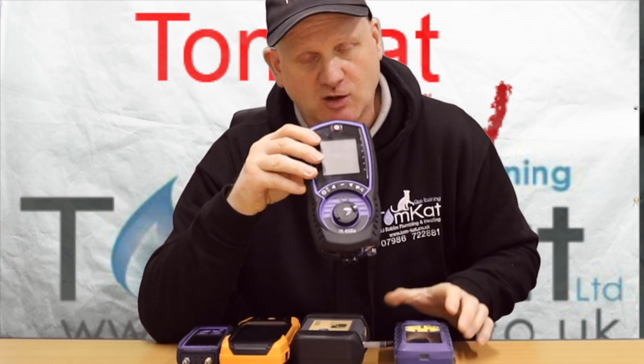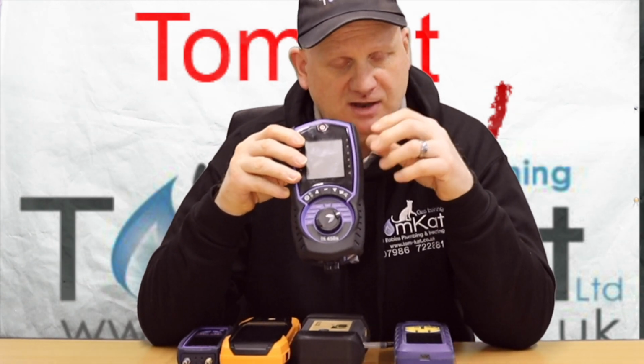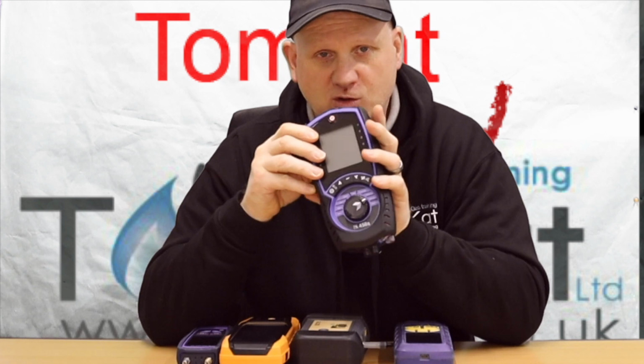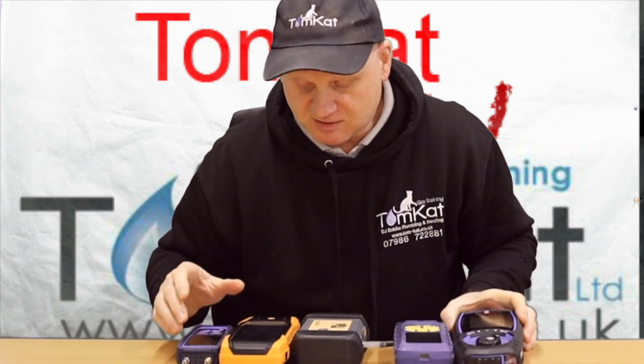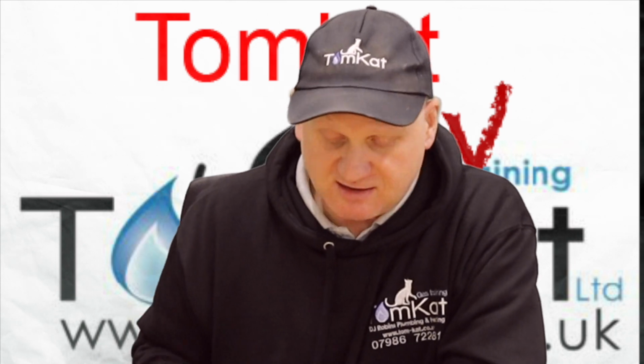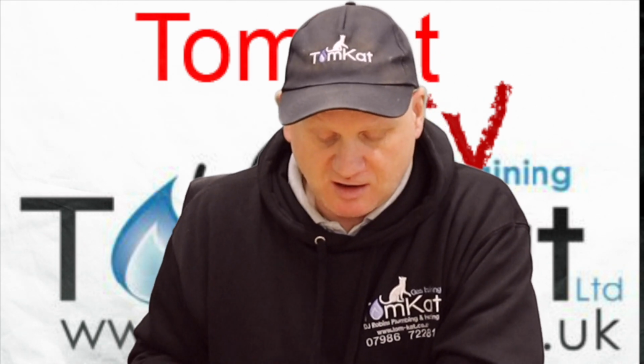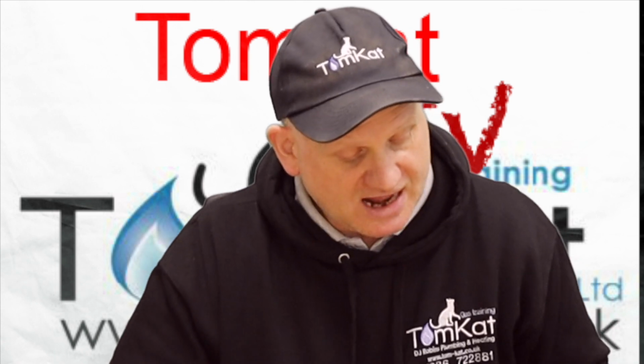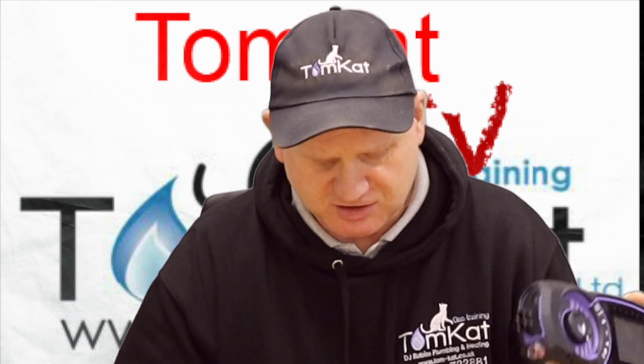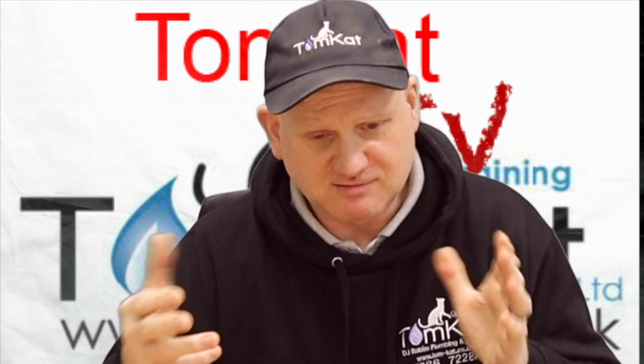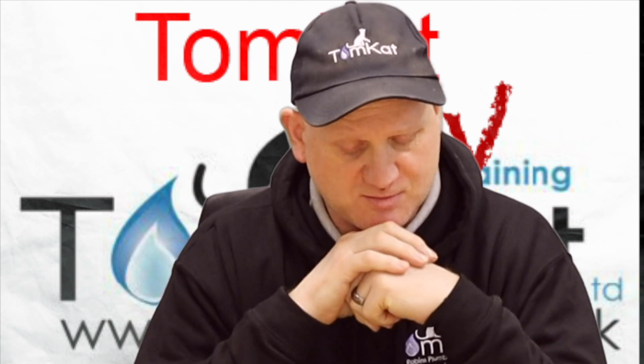If you do watch the video on which is the best between the bluelyzer, Kane and Anton, you'll find how quick this does come back. But saying that, the bluelyzer one, I sent it away for calibration on Monday and it came back Thursday. So that was a good turnaround. And I don't know how long these take to come back. So knowing the rep will help you massively as well if you get problems and if you want your analyzer going back quick. And I do know some of the reps will actually loan you them while they're away for calibration. So yeah, they're amazing. So get to know your rep, because that's the most important thing.